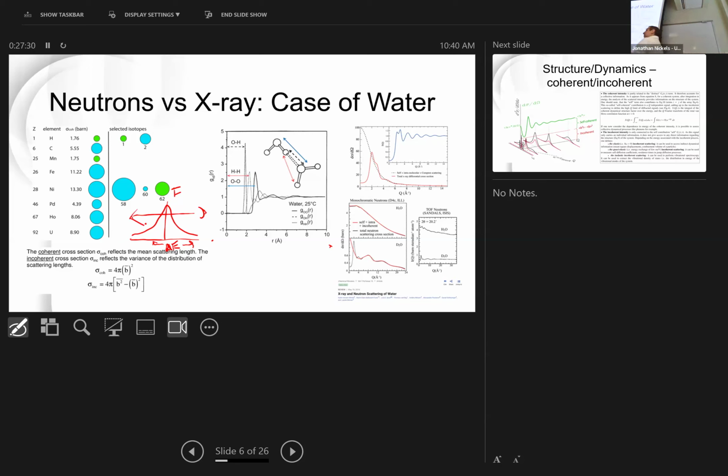This is why this is multiple scattering, this is inelastic scattering, this is a signal that compromises your SANS measurement. If you do this exact same experiment on a spectrometer, what you can do is actually isolate the incoherent signal. So this would be zero energy change, right? So that's delta E equals 0. And so if you define how much energy transfer you're willing to take, you can see only the coherent scattering and ignore the incoherent or the inelastic. Whereas most structural spectrometers, most of these instruments, are designed to ignore it.